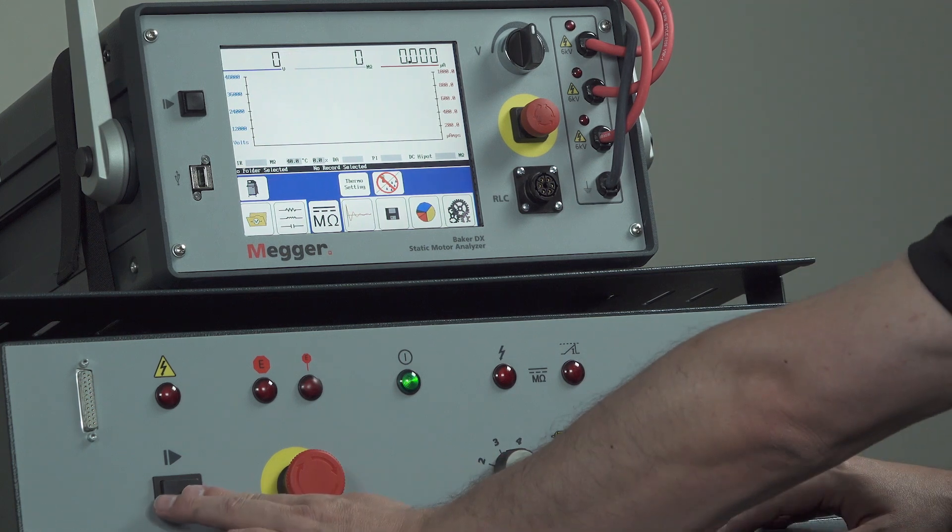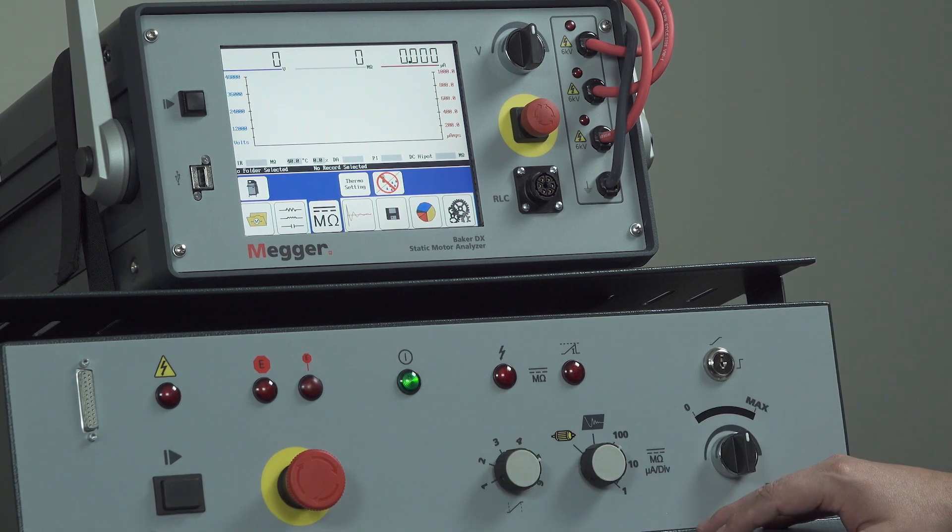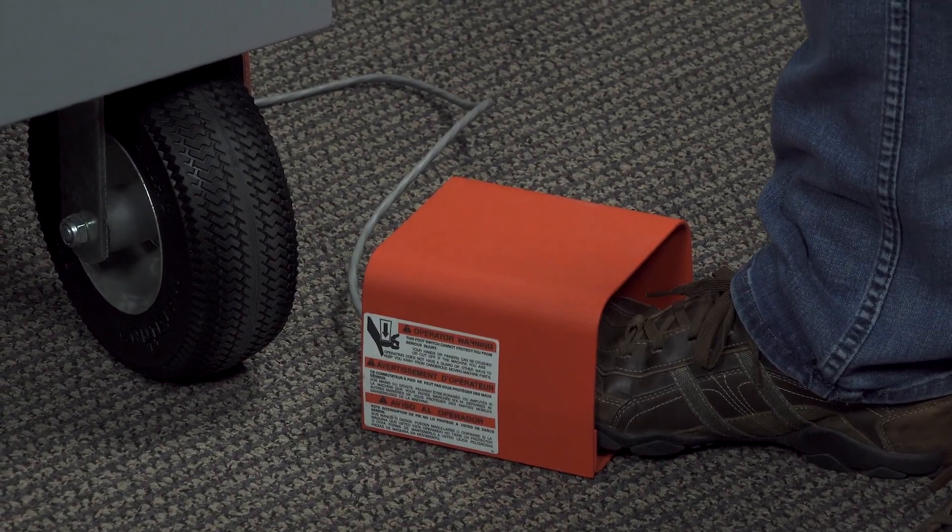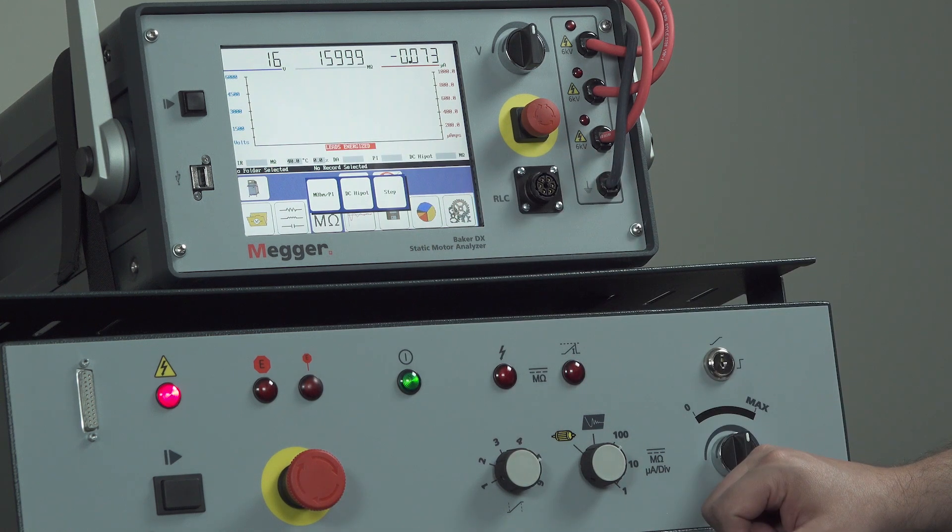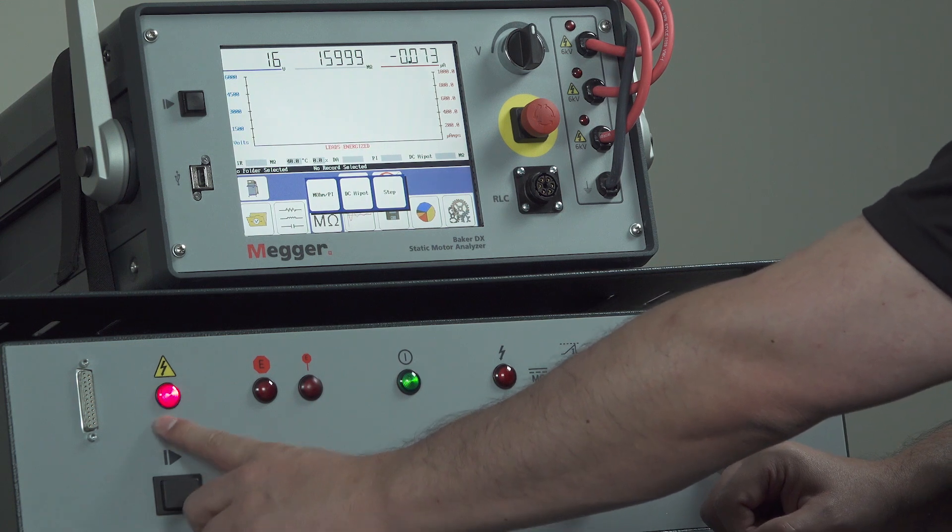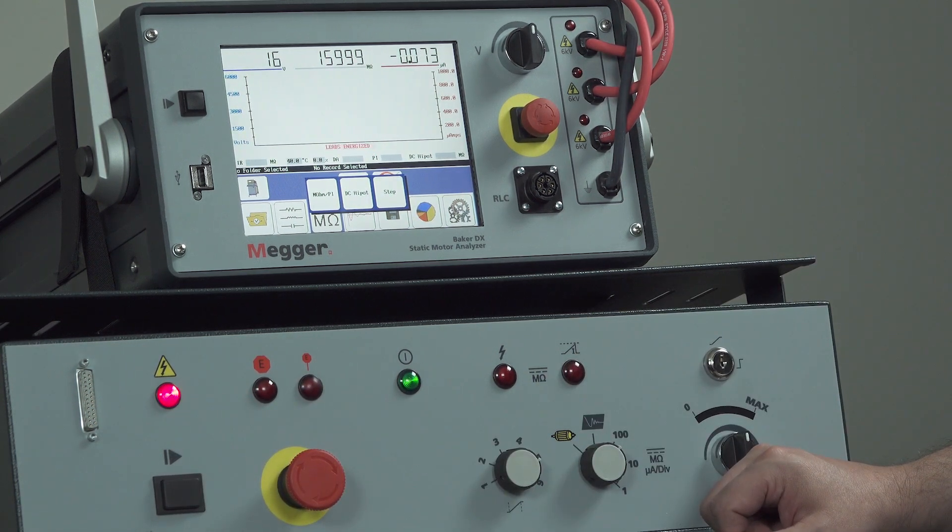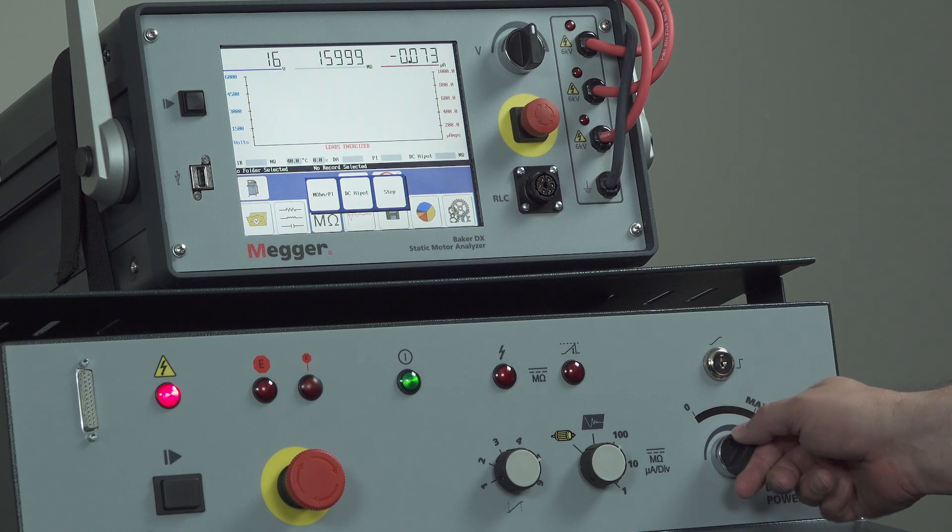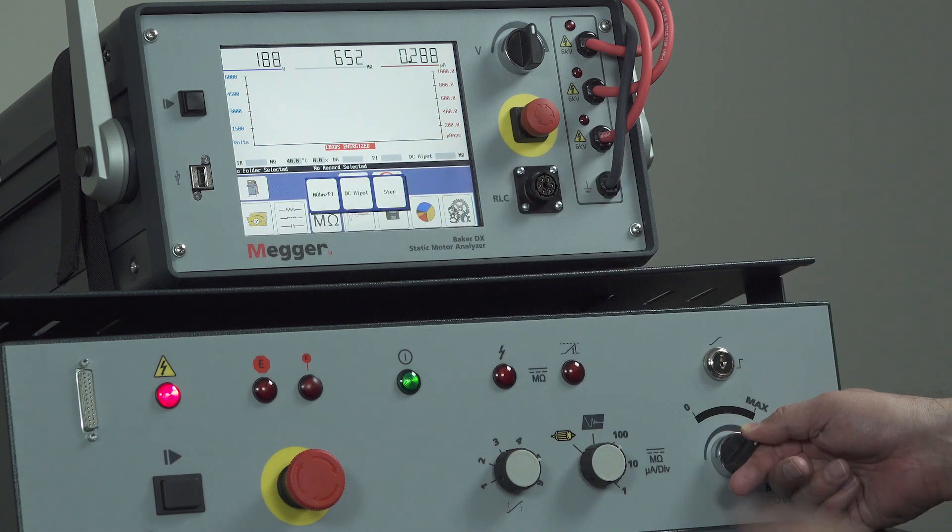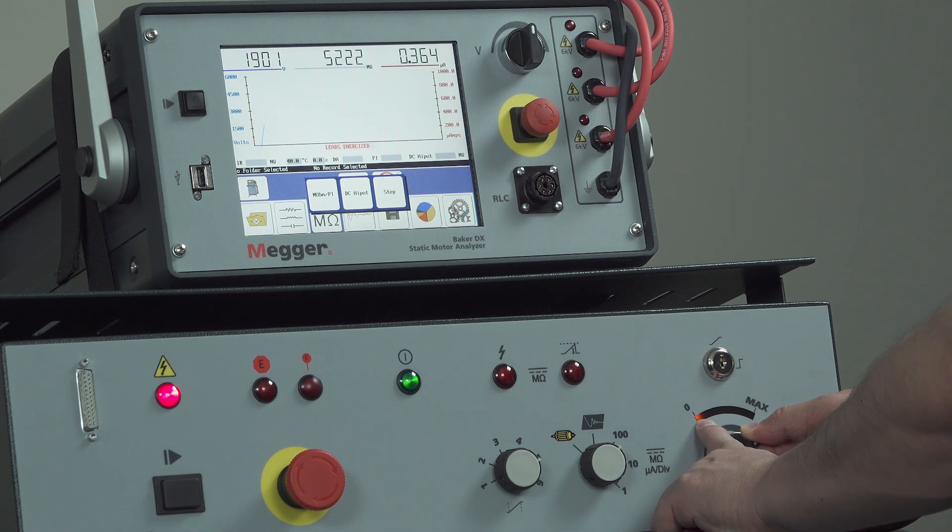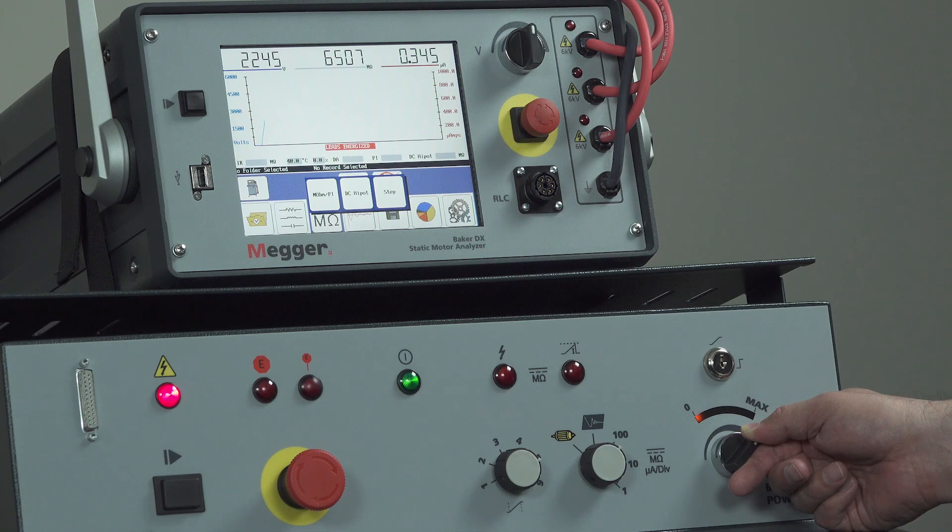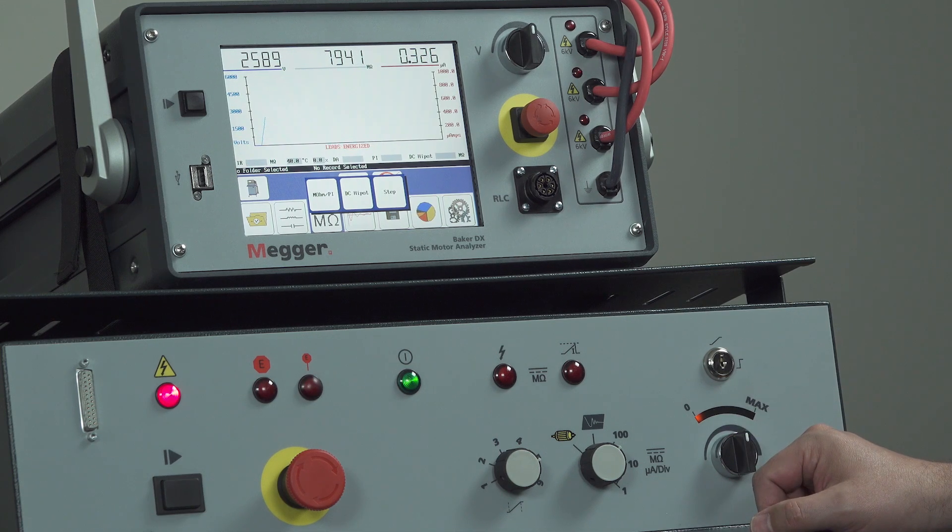To do that, we'll either press the push to test button and hold or depress the foot switch. I'm going to use the foot switch to start the test. We see the leads energize indicator there, and the leads energize light illuminated here. Now we want to ramp the voltage using the voltage control knob. We'll turn that clockwise and watch the voltage increase. We'll ramp to our first step, which in this case is going to be 2,500 volts. We also see the LEDs indicate that our voltage is increasing as well. Now we're at 2,500 volts. I'll stop ramping.